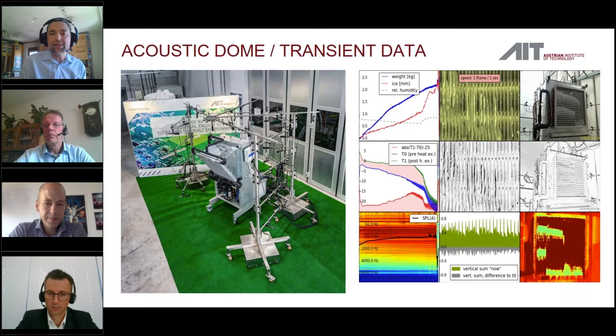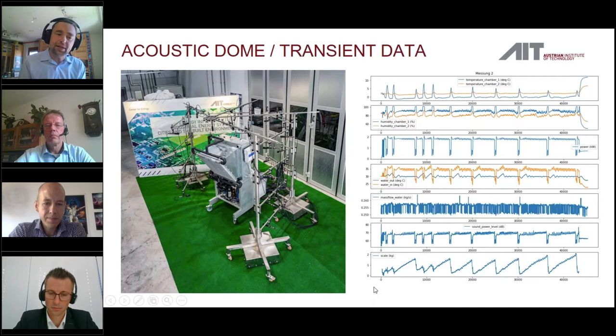You see here the defrosting of the evaporator, for example, here. And if you do this, then in addition to the typical climate chamber data—inlet temperature of the heat pump, water part, outlet temperature, humidity of the climate chamber (the outdoor situation), temperature—you get additional information like the sound power level as a function of time.